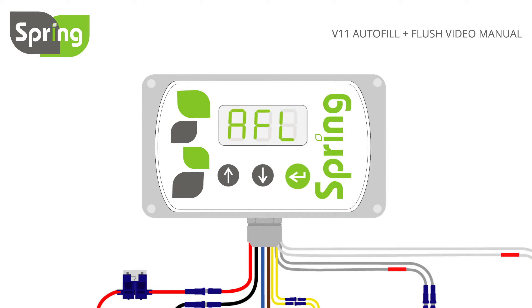Pressing enter will take you to the auto flush setting, AFL. Your controller has three auto flush modes: zero — auto flush is off; one — auto flush will repeat every hour; and two — the system will auto flush just once at the start of filling. Select the required auto flush mode using the up or down button.